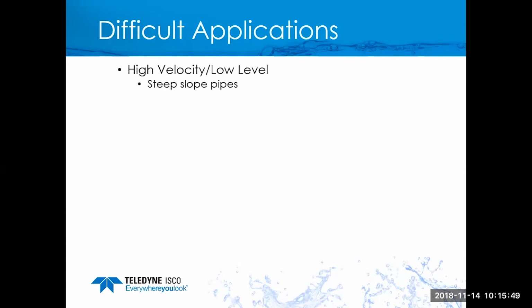But low level, high velocity is very challenging, if not impossible, to measure with a traditional in-pipe sensor. Low level raw water, wastewater velocity is always challenging because a lot of times your water goes below 1 inch. Well, in the case of most area velocity sensors, we get readings above 1 inch and then we interpolate below 1 inch, but it's semi-made up data because it can't read less than 1 inch. The laser can read much lower level than that.